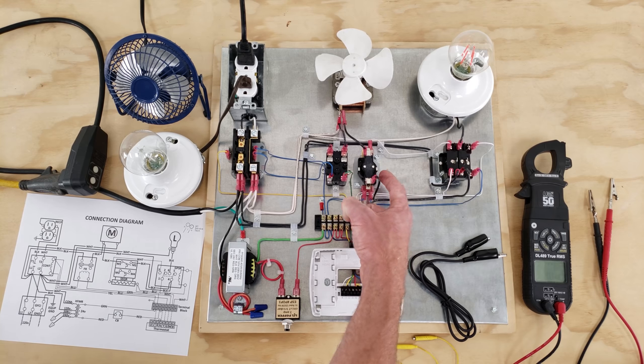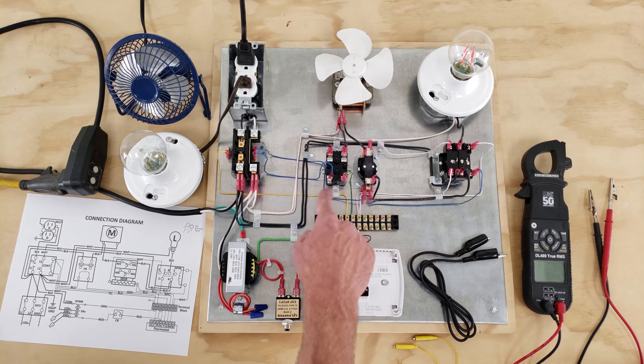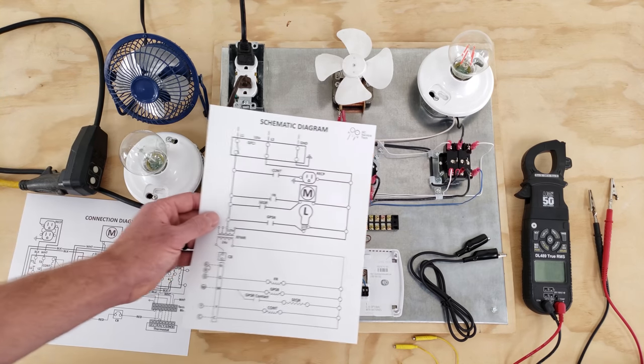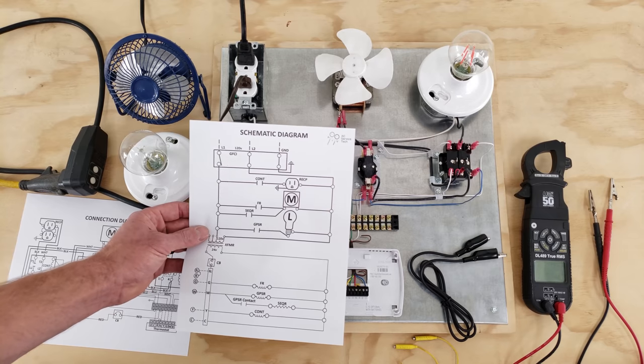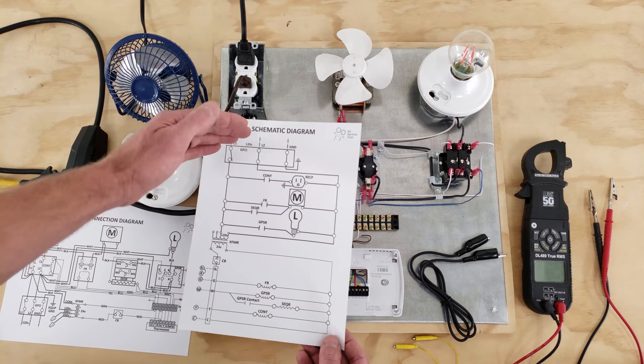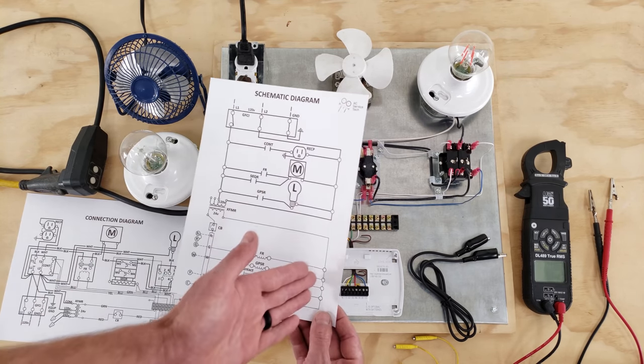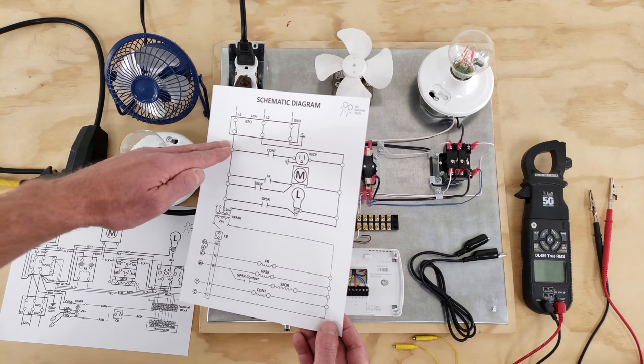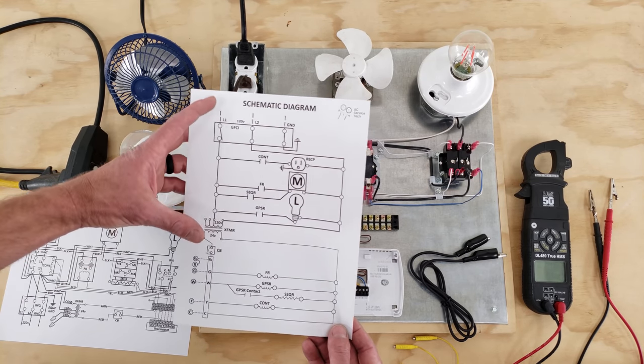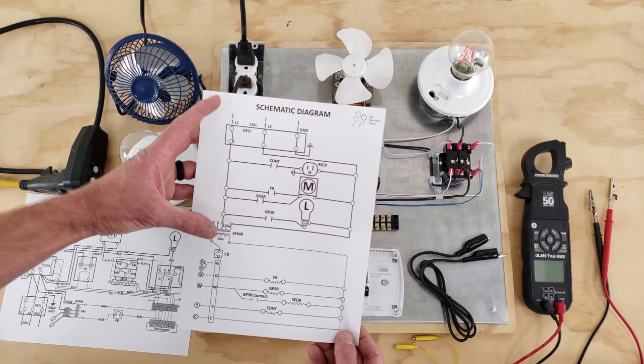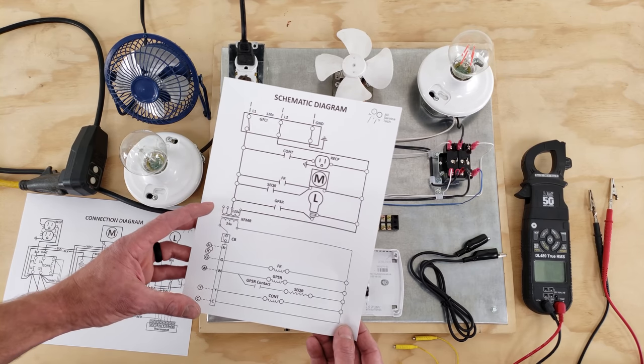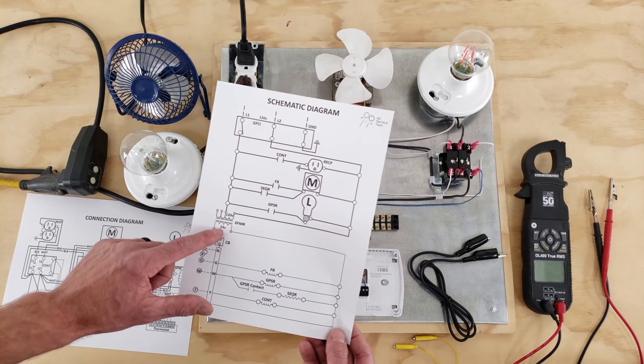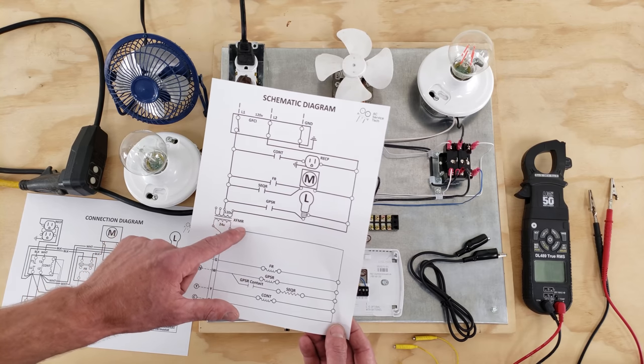It has a pan heater at the bottom, so there is not an electromagnetic coil such as in the bottom of this one, and this one. Now, as far as a schematic diagram goes, a schematic diagram, in this case, is a ladder diagram. See the ladder, the two sides of the ladder, and right here you have each of the horizontal sections. The top part of this is going to be your high voltage, and then your lower section is your low voltage, signified by your 24 volt at your XFMR.